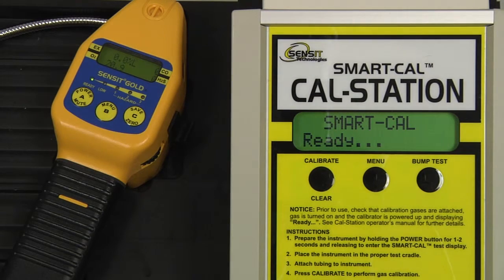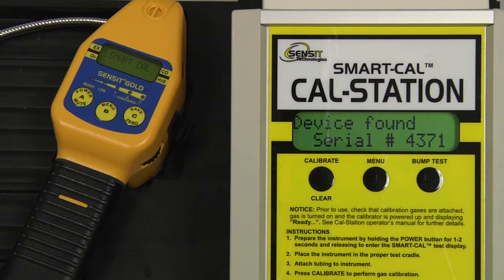To begin, place the instrument in the cal station cradle, attach the instrument hose to the end of the gooseneck, and enter into SMART-CAL mode by pressing and holding the A button for approximately 2 seconds and releasing. Press and release the calibrate button on the cal station, and the process will begin. Our device has been found. There will be a flow check, followed by a 60-second purge. After the purge is complete, the instrument will auto-zero and the calibration will begin.